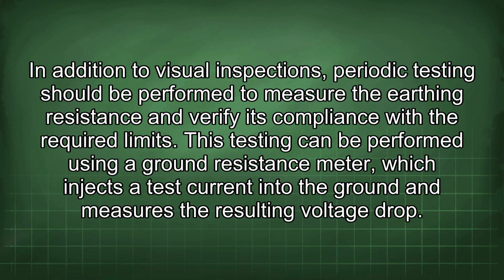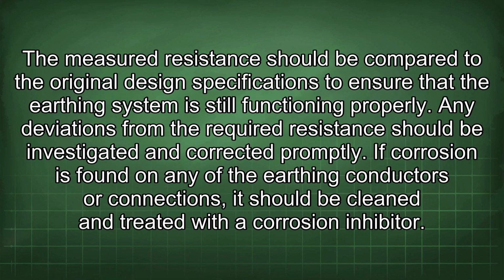In addition to visual inspections, periodic testing should be performed to measure the earthing resistance and verify its compliance with the required limits. This testing can be performed using a ground resistance meter, which injects a test current into the ground and measures the resulting voltage drop. The measured resistance should be compared to the original design specifications to ensure that the earthing system is still functioning properly. Any deviations from the required resistance should be investigated and corrected promptly.